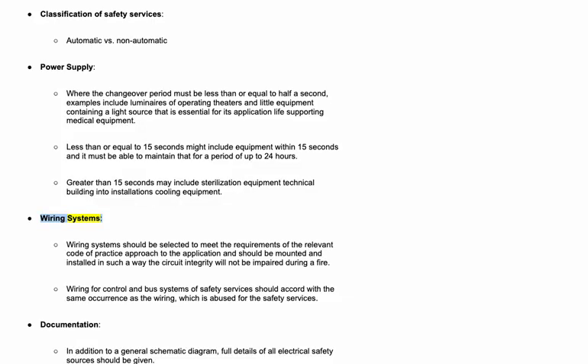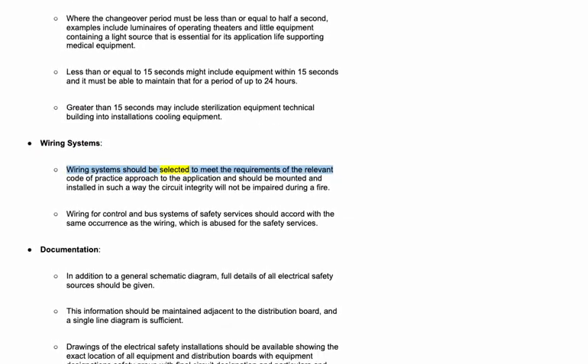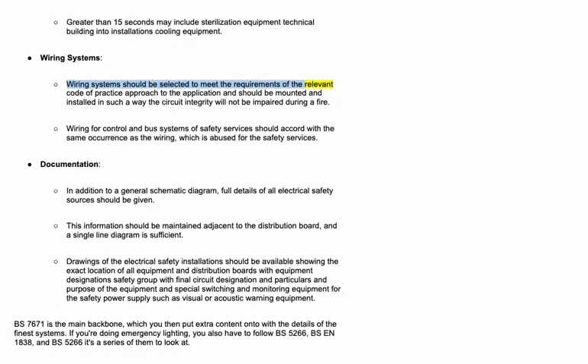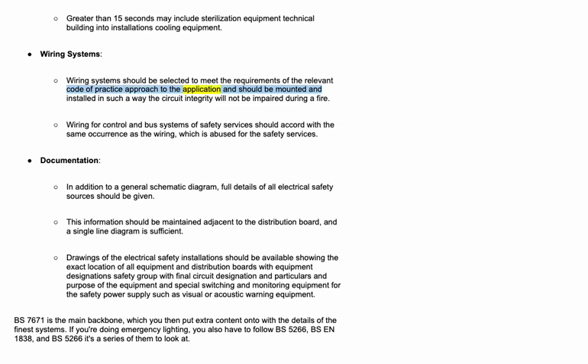Wiring systems. Wiring systems should be selected to meet the requirements of the relevant code of practice, appropriate to the application, and should be mounted and installed in such a way that circuit integrity will not be impaired during a fire. Wiring for control and bus systems of safety services should accord with the same requirements as the wiring used for the safety services.